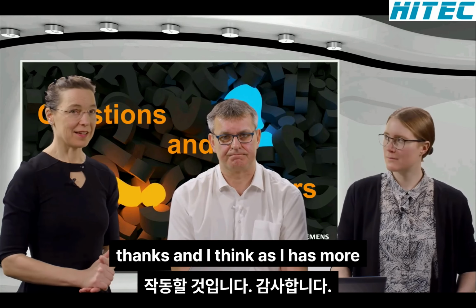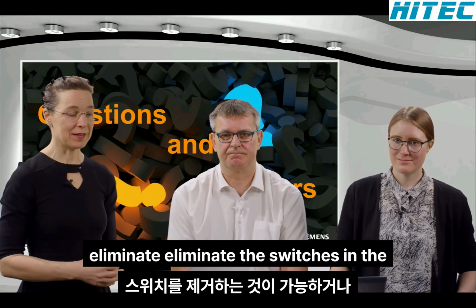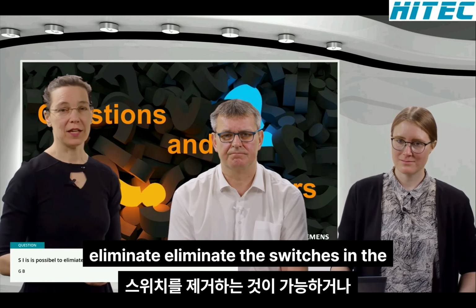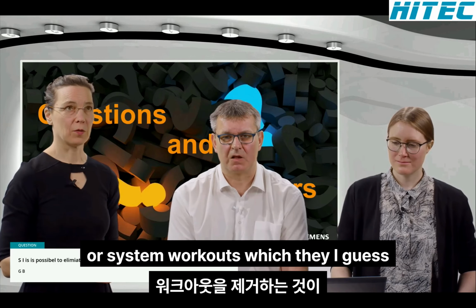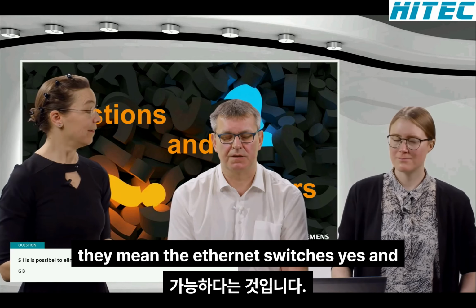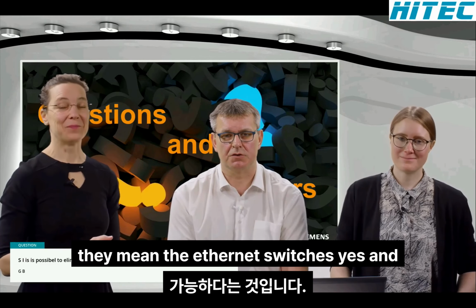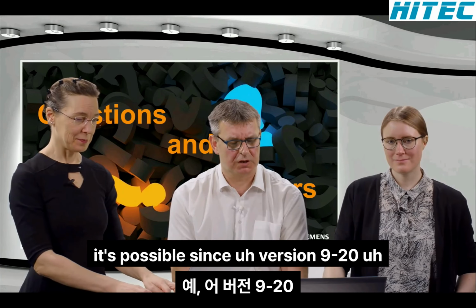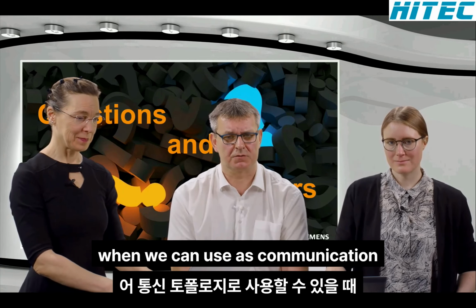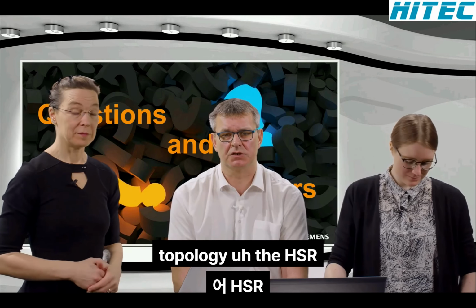And I think as SI has more questions, the next one is: is it possible to eliminate the switches in the centralized system? Or a system without switches? I guess they mean the Ethernet switches, yes. And it's possible since version 9.20, when we can use HSR as communication topology.